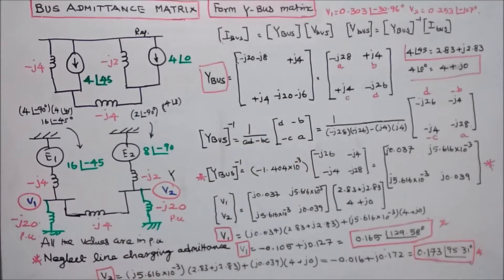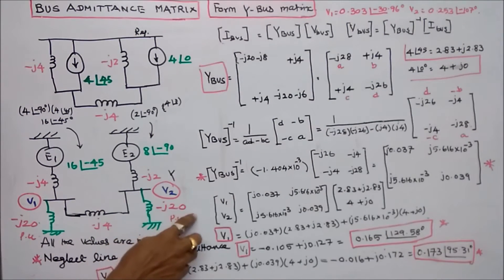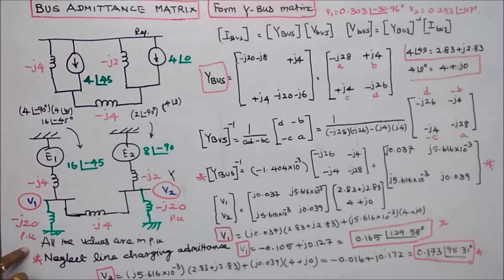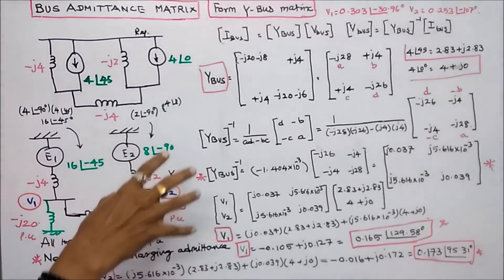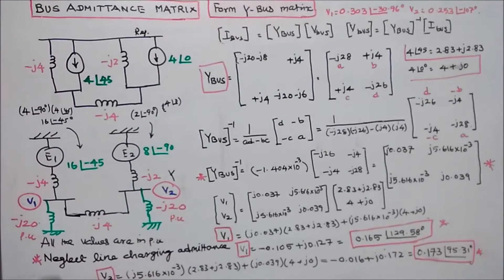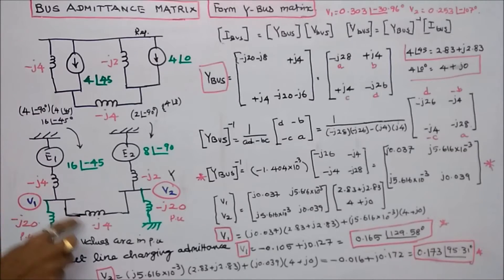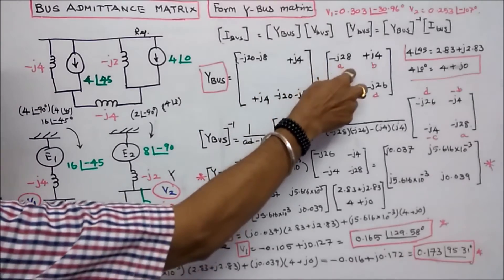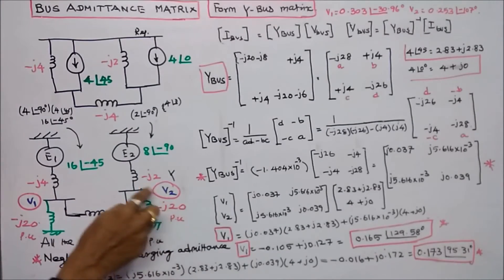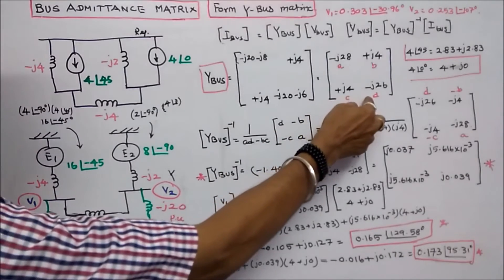In the same problem, I remove the capacitor and add a shunt reactor of minus J20 per unit at each bus. The question is to form the Y-bus matrix and find bus voltages V1 and V2. At bus 1, three elements: minus J20, minus J4, minus J4, giving minus J28. At bus 2, three elements: minus J20, minus J2, minus J4, giving minus J26.